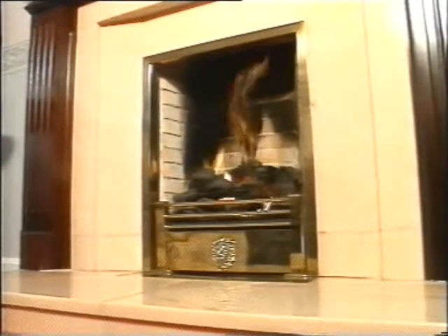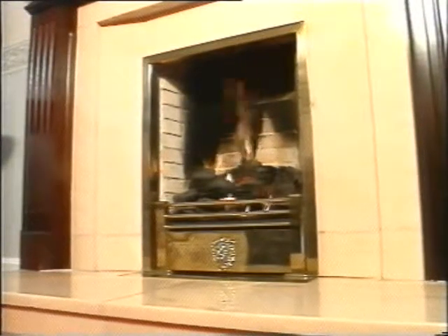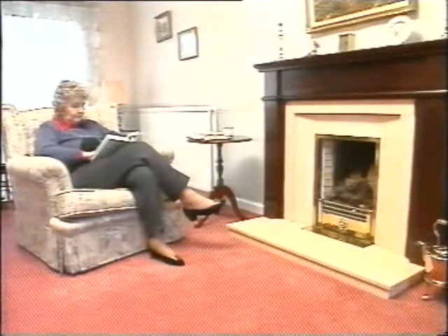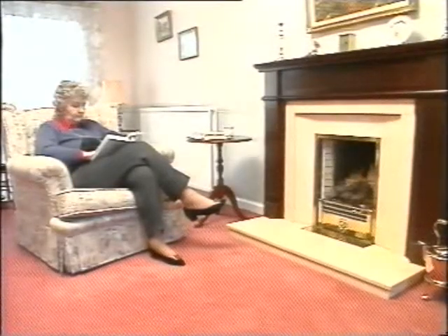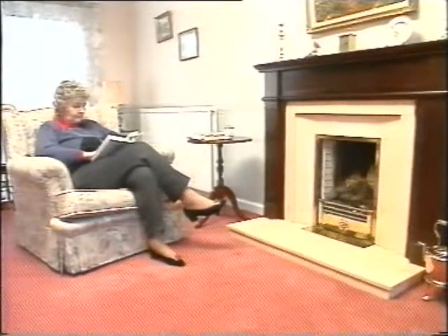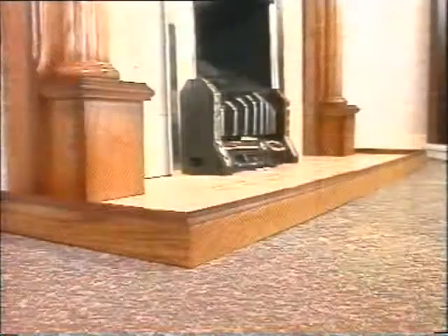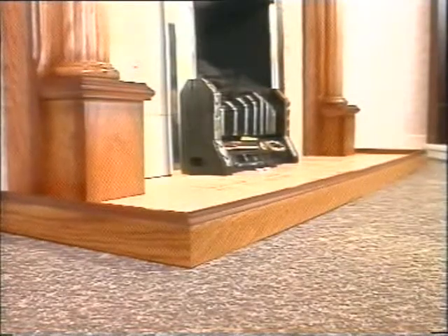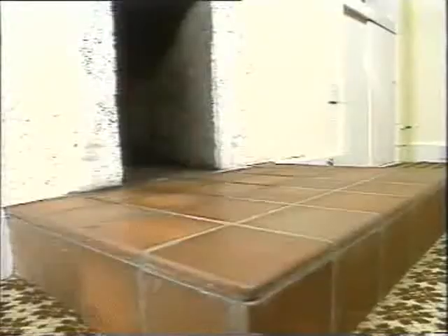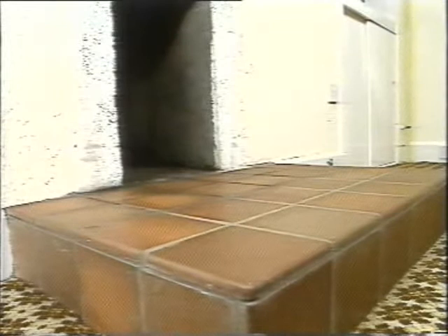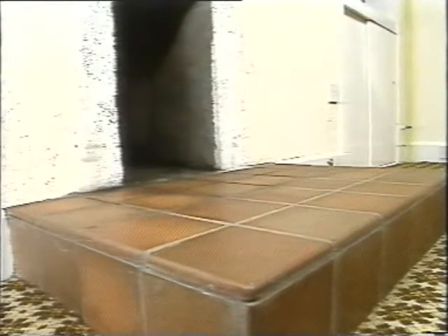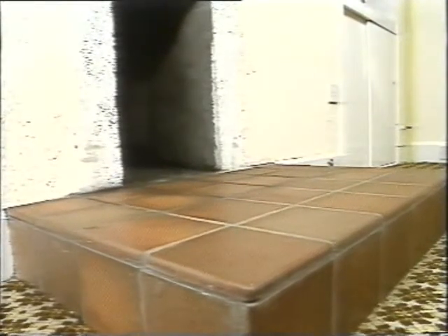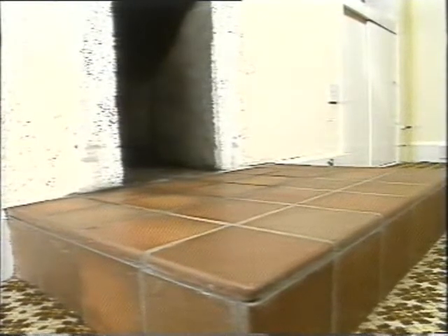Let's start with the location. Gas fires can't be installed in any room or internal space where there's a bath or a shower. They must be on the hearth or the floor, or else fixed to the wall. If there's a hearth, it must be made of non-combustible material, at least 12 millimeters thick, and extend at least 300 millimeters out from the fire and 150 millimeters on each side of it.